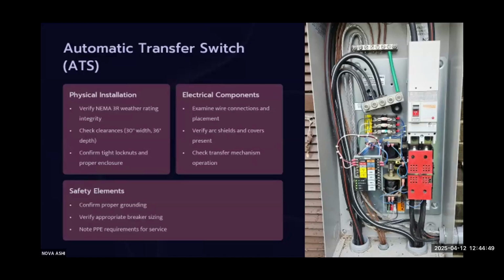A great thing to look at is the lock nuts. Where you see these conduits coming into the ATS, into this housing, you have these male adapters from the PVC that's coming in, and each one has a lock nut around it. You want to make sure that they are tight, because anytime you have any loose connection, either from the enclosure or the conduits, it's potential that the wires may become loose. And when the wires become loose, next thing you know, you may have a little bit of charring. So you lose the ampacity.